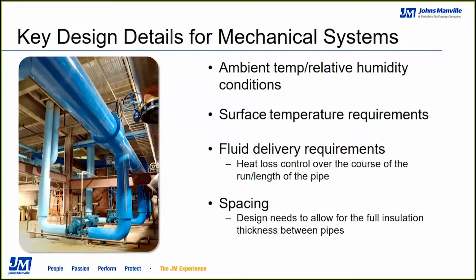Surface temperature requirements are also very important. As previously mentioned, the OSHA limitation for safe-to-touch surface temperature is under 140 degrees. Fluid delivery requirements will determine how much heat loss or gain is acceptable over the length of the system, and ultimately the performance required for the equipment. And sometimes overlooked, spacing required between pipes to allow for the proper insulation thicknesses.